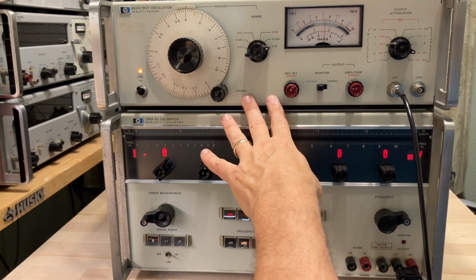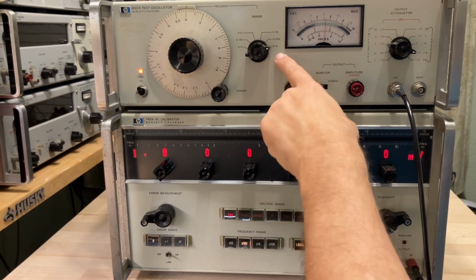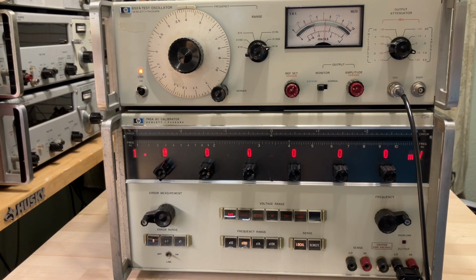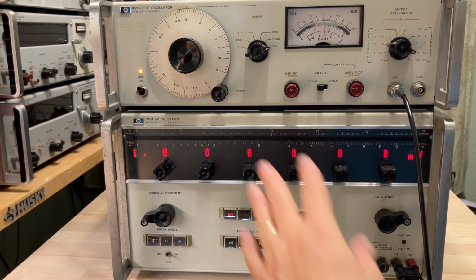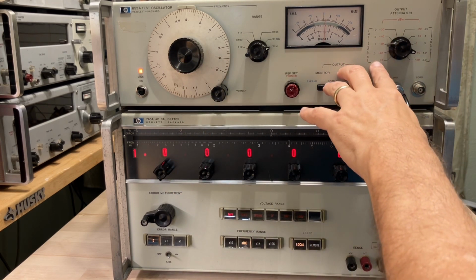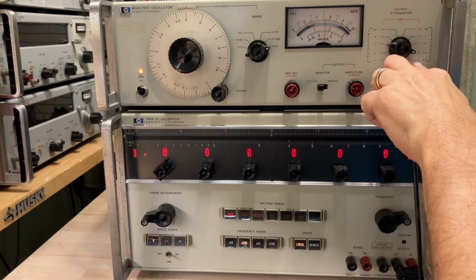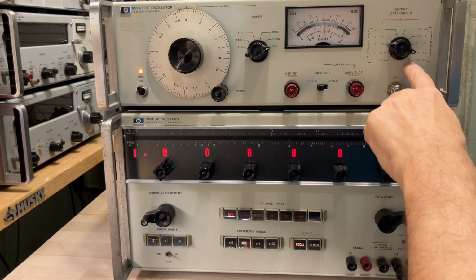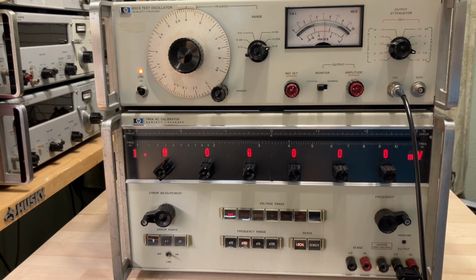This is a 652A test oscillator. It goes from 10 hertz to 10 megahertz. So it can be used to test high frequency response of AC voltmeters. And that's what we used back in the 1980s to test these voltmeters like the one I'm working on today. This one goes from 1/10 of a millivolt full scale all the way up to 3 volts full scale. I can't test higher than 3 volts above 110 kilohertz using these two instruments. So I can test every range and every frequency on this instrument except for the 300 volt range. I don't have a calibration standard that can output 300 volts AC at this time.